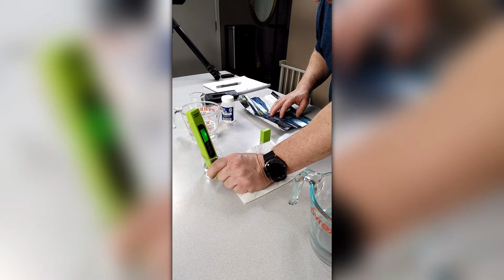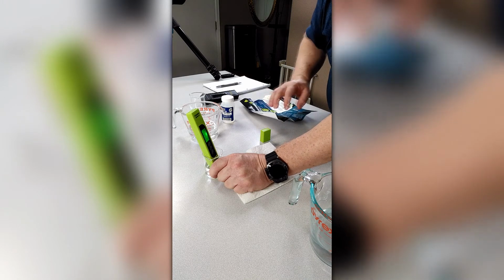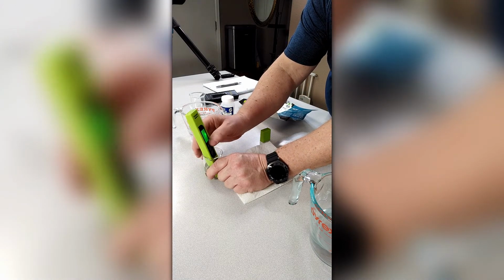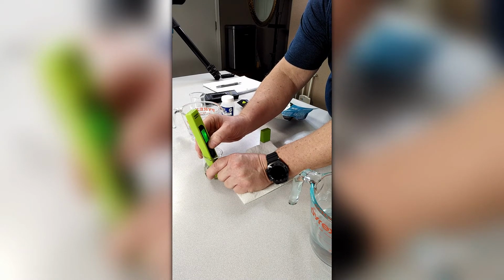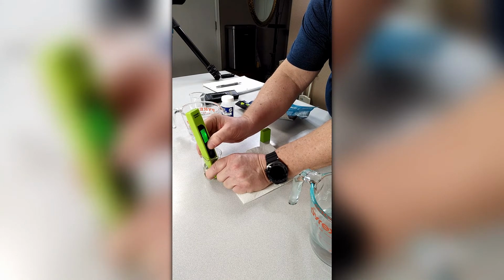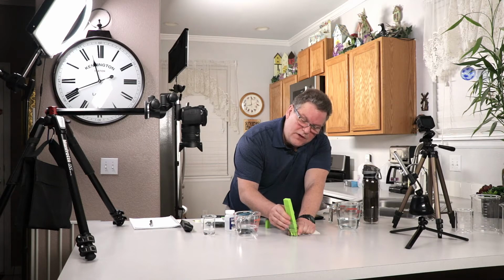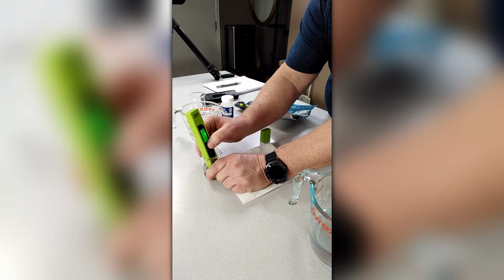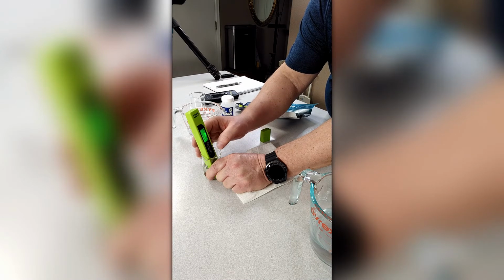And it says adjust the result by pressing the on-off button to increase the result value. Okay, so it's at 856, 857. We're going to keep pressing that until we get up to like 999 or 1,000. This meter says it'll read up to 10,000 parts per million. I don't know what that is. Molten lava? Getting very close now. It's 998. There we go.